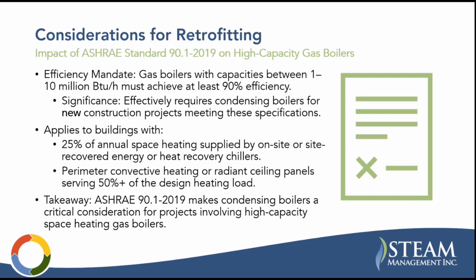Other considerations, ASHRAE 90.1, the 2019 version, came out with recommendations that gas boilers with capacities between 1 and 10 million BTUs per hour, which is a lot of these commercial boilers, effectively require 90+% efficiency for new construction. So they're basically requiring condensing boilers in this standard. So that's the takeaway, that now we're not talking about retrofits, but it is just an indication that the standards are moving in this direction where condensing boilers are going to be required in a lot of applications.